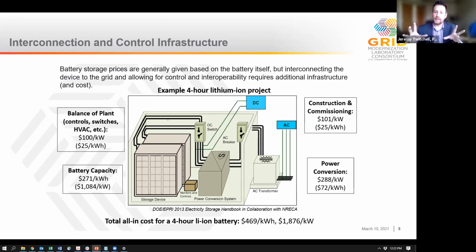So the point is that the total all-in cost for a 4-hour lithium battery, down at the bottom there, is about $469 per kilowatt hour. That battery component we usually see cited as the cost of a battery only represents somewhere between 40 and 50% of that. These costs vary significantly depending on the project and circumstances, but the battery cost is usually about 40 to 50% of the overall system cost.